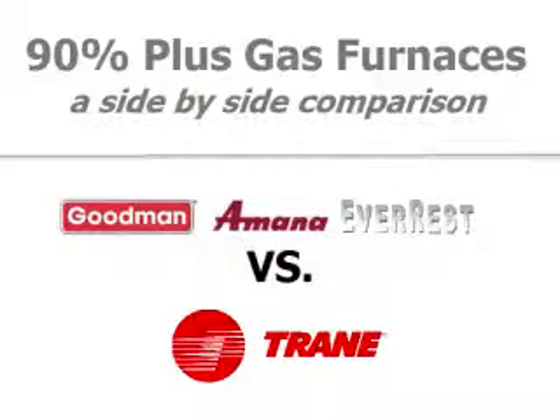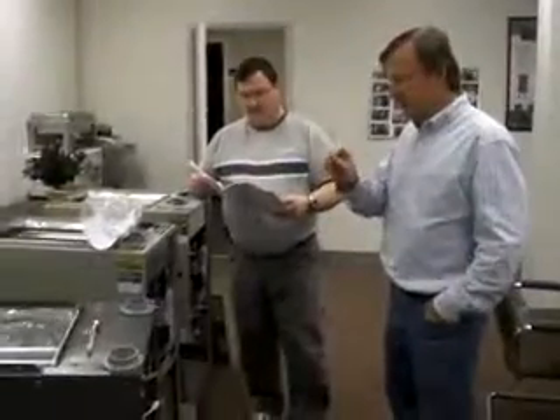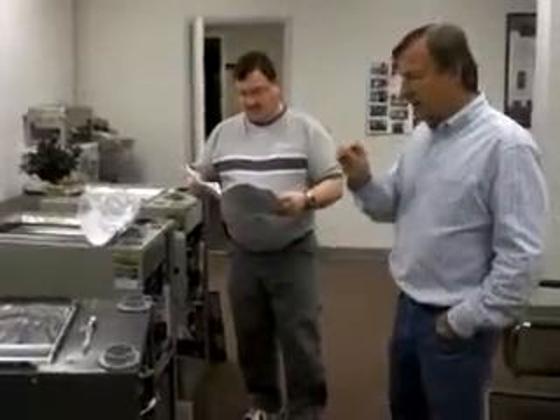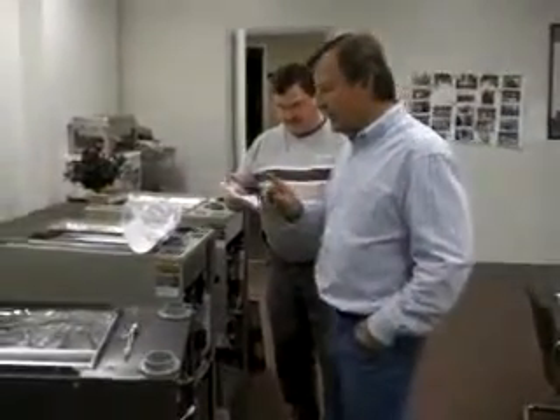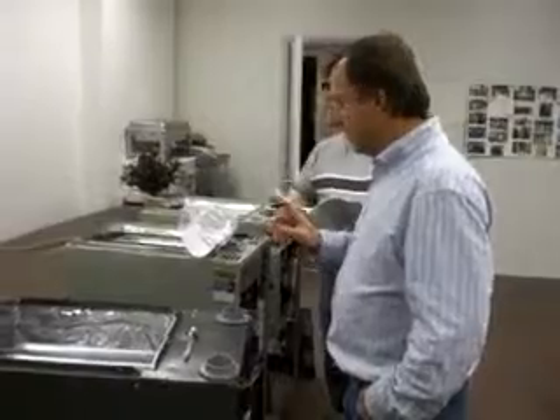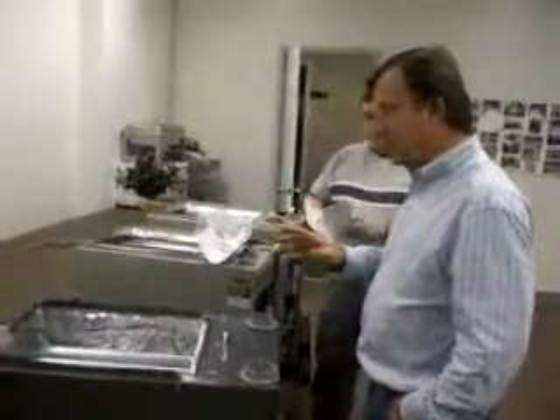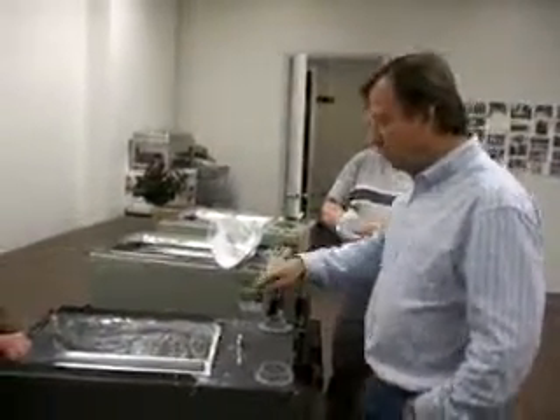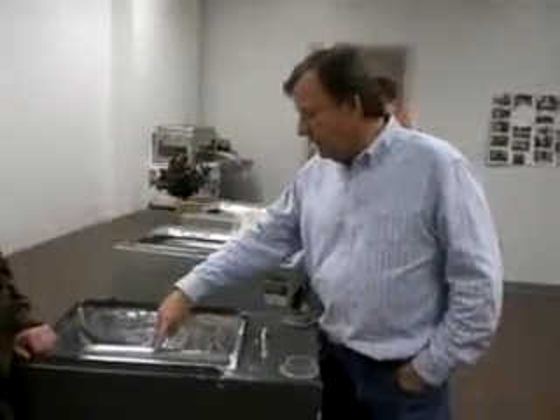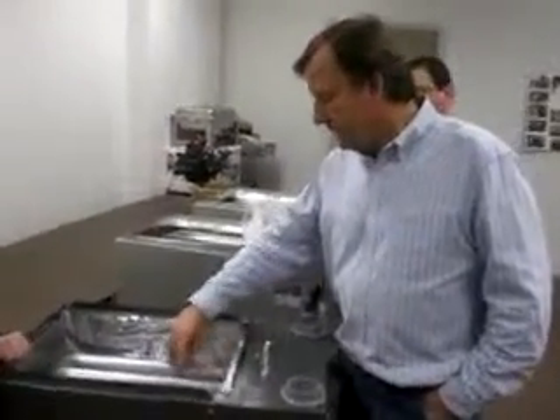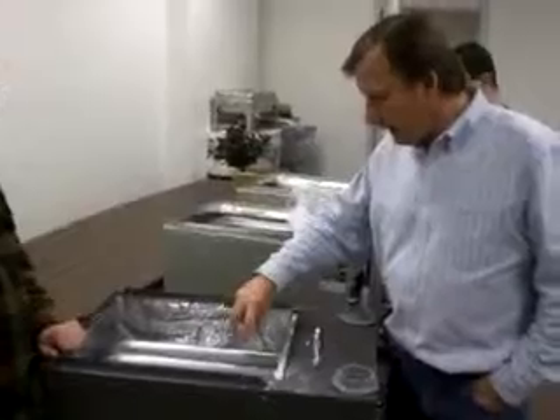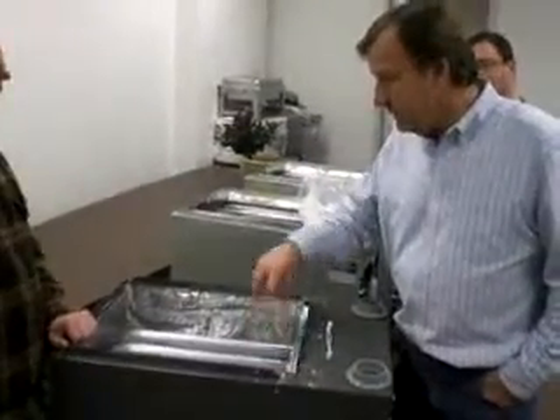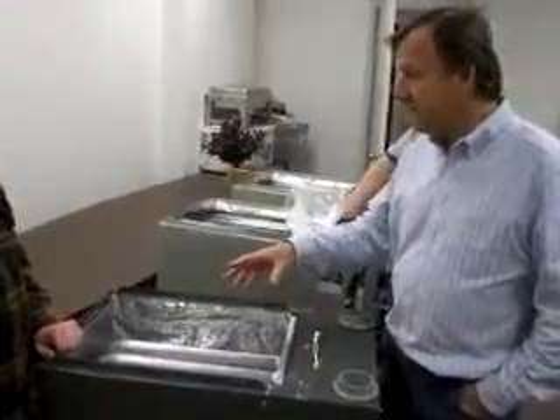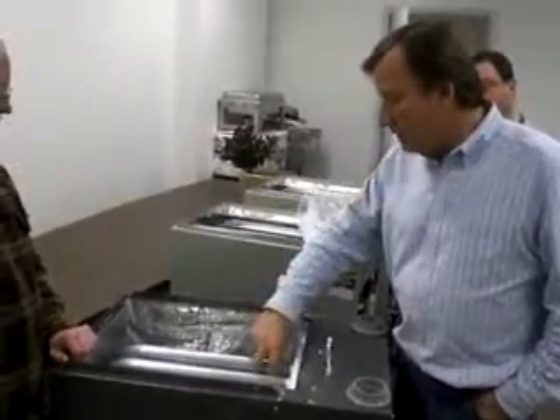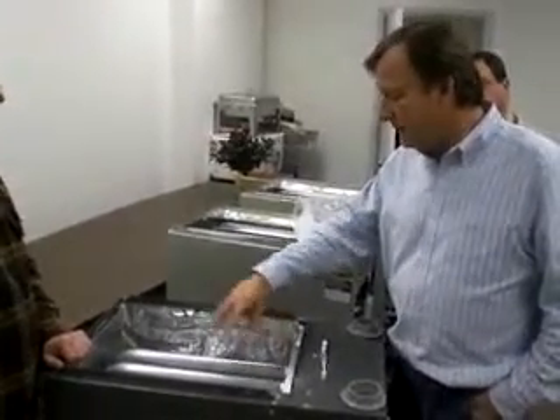One of the issues we had to overcome was that Amana Goodman has done a fairly successful job at telling dealers that they have a better design because of a few things that they say are better. One of them is the tubular heat exchanger. Okay, the tubular heat exchanger has a very limited amount of surface area. It's smaller, it's more constricting.